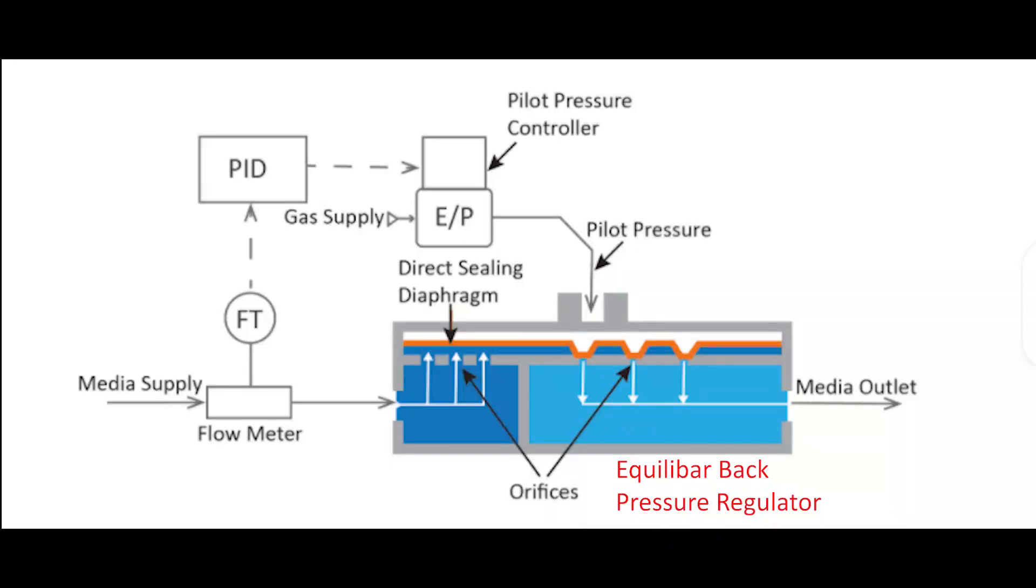The Equilibar back pressure regulator is used to control pressure upstream of the device by using a one-to-one pneumatically loaded set point on the dome of the regulator. A direct sealing diaphragm in the dome of the unit covers a field of orifices and adjusts its position to allow flow through the orifices to maintain a desired pressure set point.